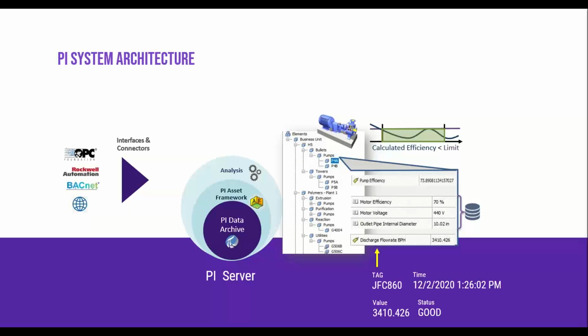Moving forward, we implemented analysis that helps us aggregate more value from the measured data. So now we not only measure and store information, but we also do analysis. For example, we calculate pump efficiency, but we can calculate really complex equations using analysis. Next, we implemented event frames, which are kind of alerts that help us identify, using different tags or attributes, patterns or bad behaviors for the equipment.